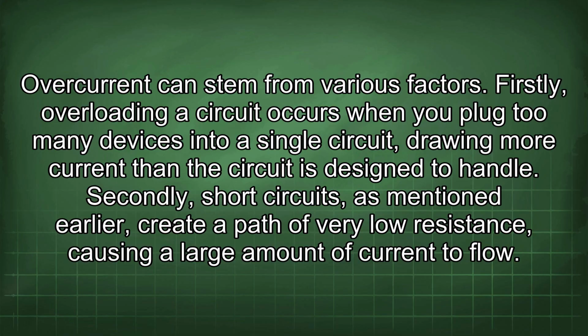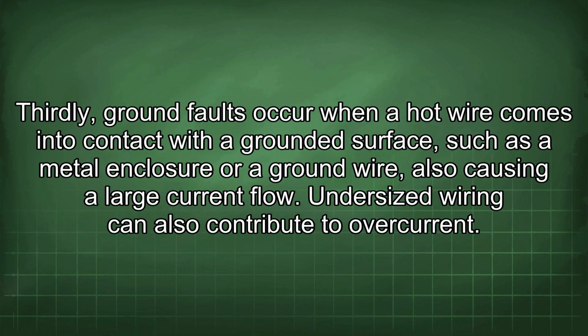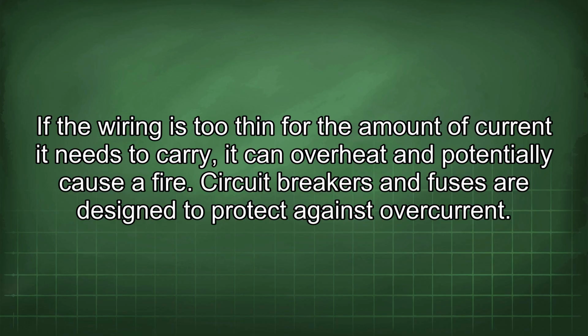Secondly, short circuits, as mentioned earlier, create a path of very low resistance, causing a large amount of current to flow. Thirdly, ground faults occur when a hot wire comes into contact with a grounded surface such as a metal enclosure or a ground wire, also causing a large current flow. Undersized wiring can also contribute to overcurrent. If the wiring is too thin for the amount of current it needs to carry, it can overheat and potentially cause a fire.